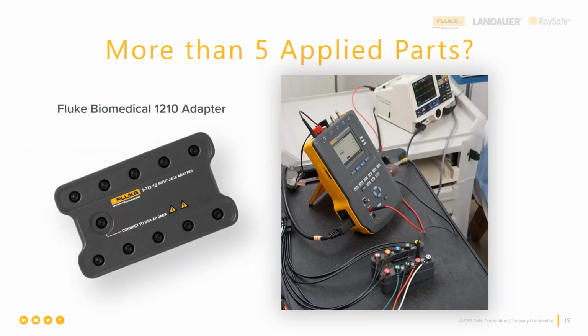Well, what happens if, you'll note, we have 2 or 3 electrical safety analyzers that we sell that only have 5 lead posts across the top. And so the question is, well, what if I'm testing a defibrillator, or what if I'm testing a 12 lead EKG cart that has 10 ECG leads? Now what do I do? Well, we're allowed under the standard to short together all of a patient connection type, which would be like a B, like a temperature lead, a BF or CF, which could be ECG leads and other leads.